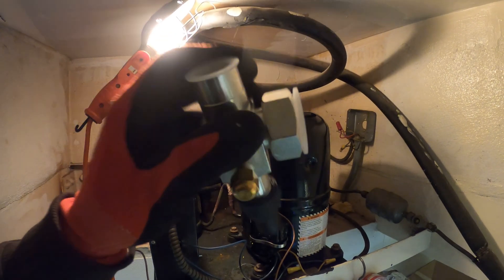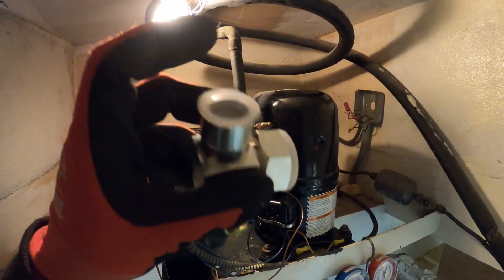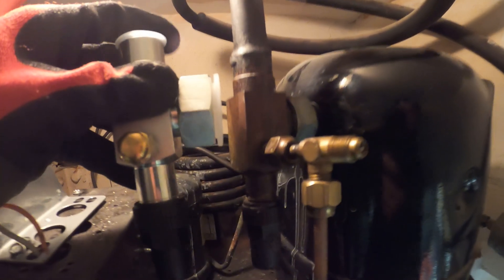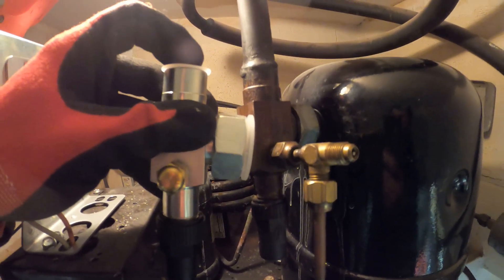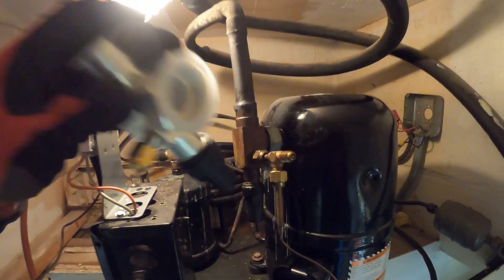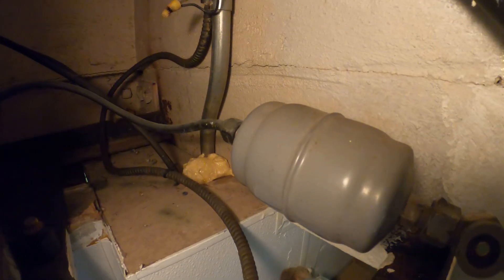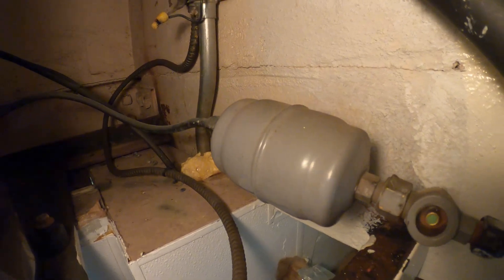Here is the new suction service valve. This is a special rotalock connection for the compressor, and what's interesting is that this is a fully steel body, so we're going to be connecting copper with steel. We're going to be replacing this valve, and at the same time, every time we open up a system due to moisture, we're going to be replacing this filter dryer.